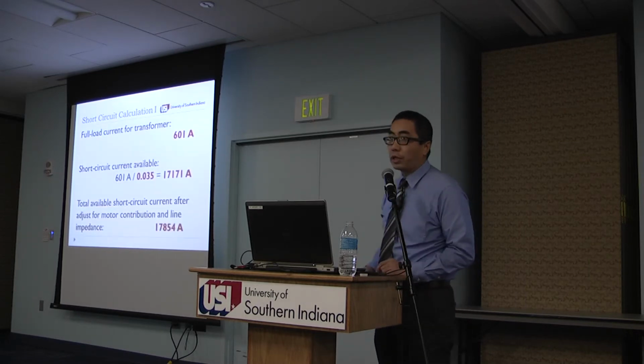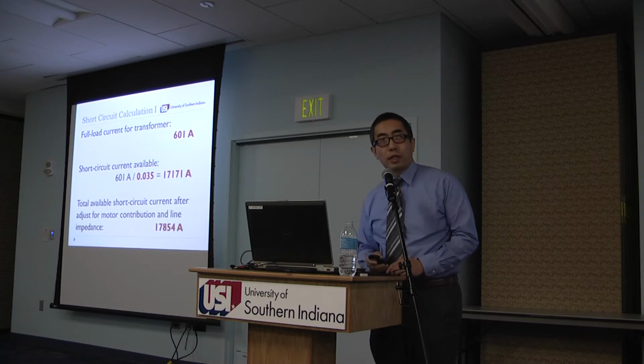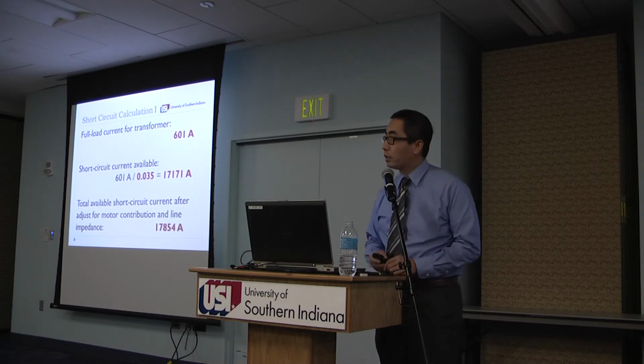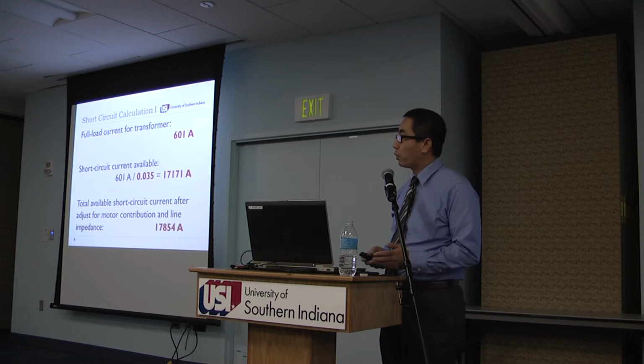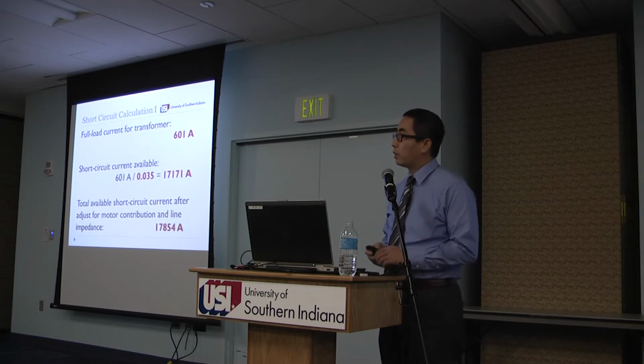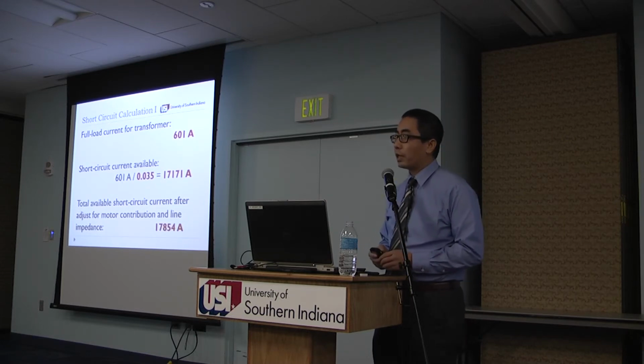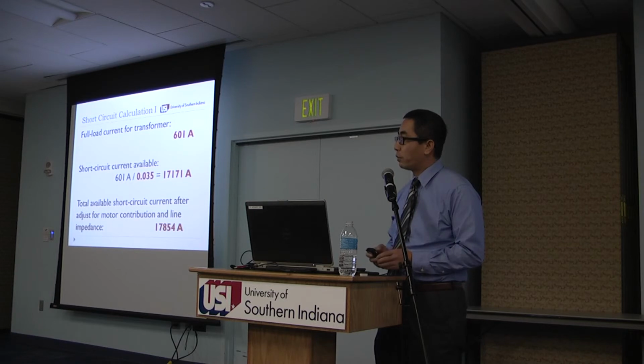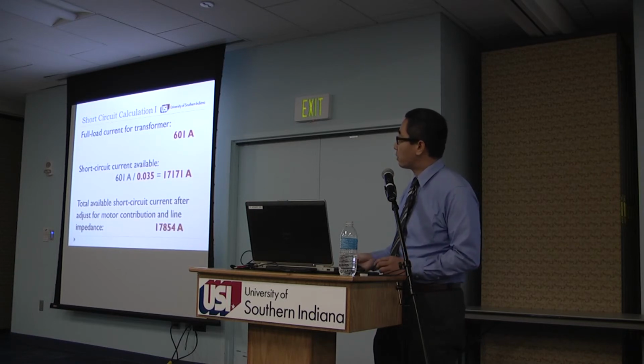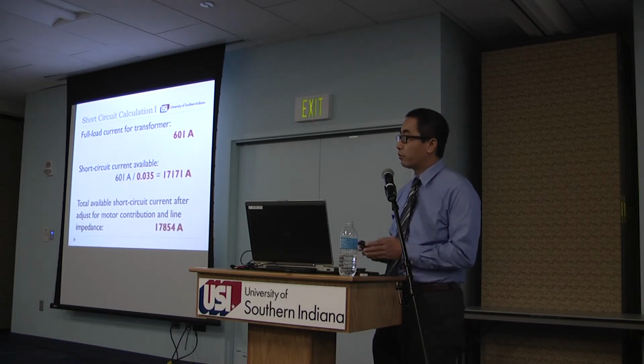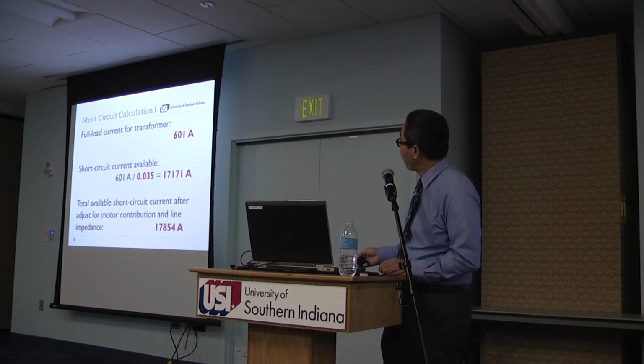And the last thing we need to check, for all the transformers, is the short circuit current. If a fault happens at a certain equipment, there will be short circuit current through the whole system. The breaker and the fuse can protect the system, but it takes time for them to trip. So you need to design a system to withstand that short period of short circuit current.